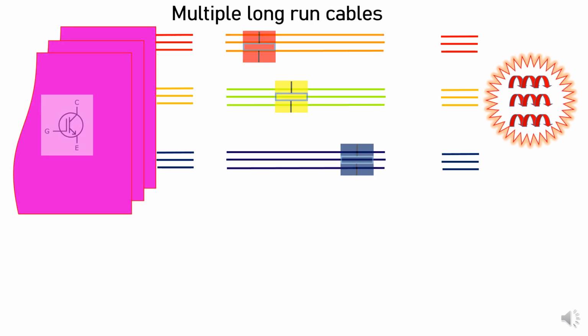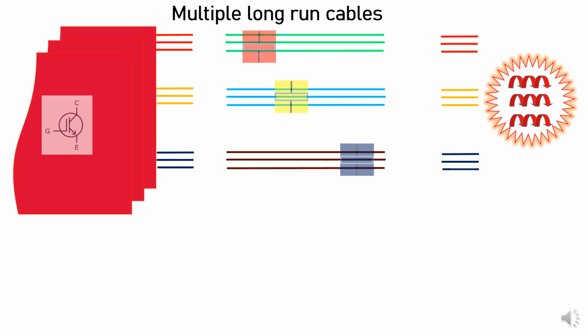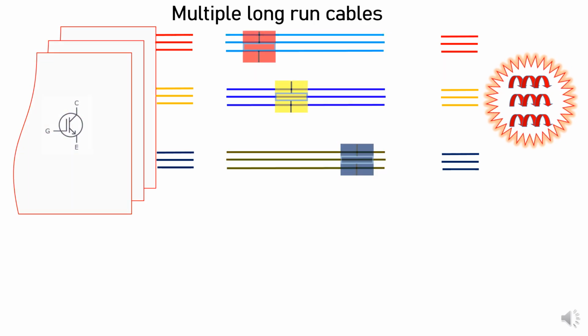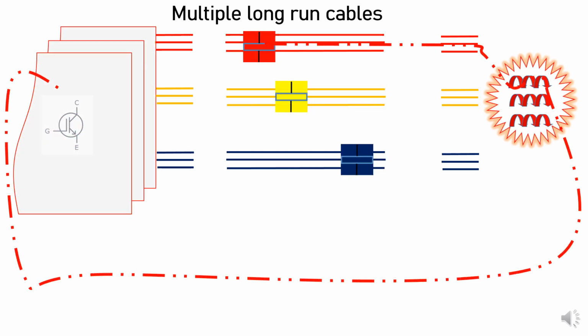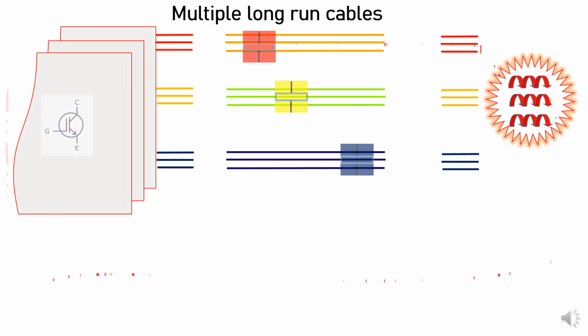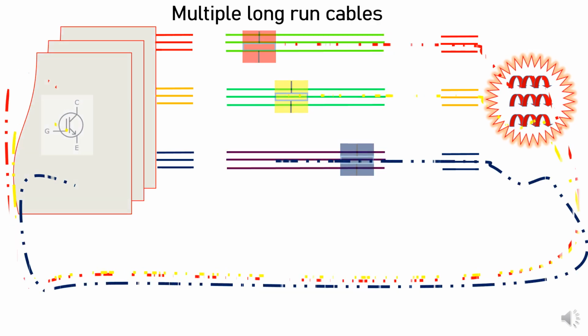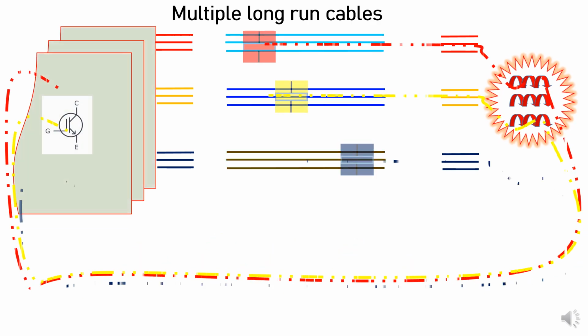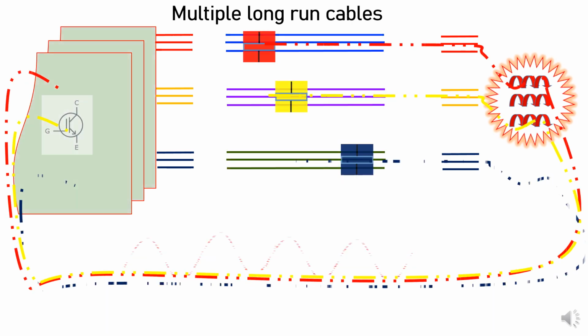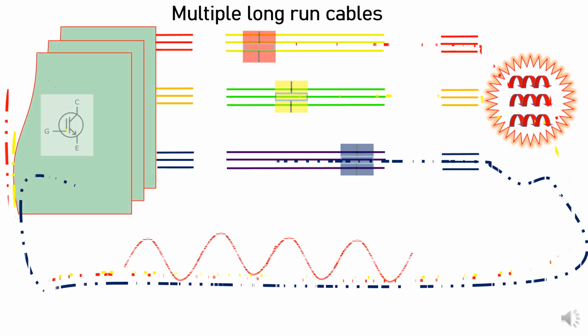The second problem is, now let me try to explain the second problem. With a simple run, simple straightway connection, you can see the capacitive current magnitude is also increased. Now if you see this, each cable is supposed to generate the capacitive current, and with the increment of the cable length, you can see here all these are additive in nature. And one beautiful day, your inverter has to handle the load current with the capacitive current, and this is because of the long run cable with the capacitive current.